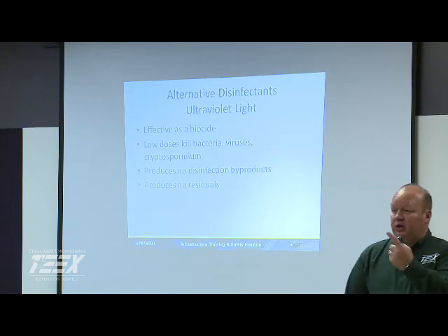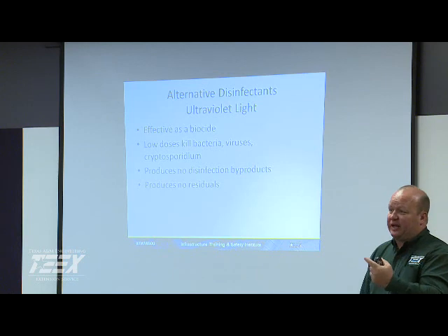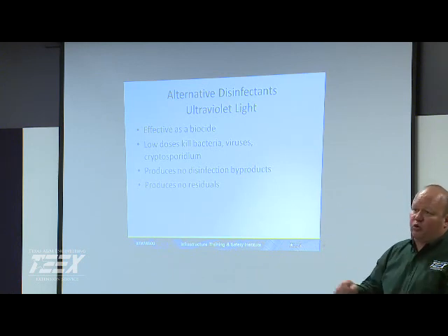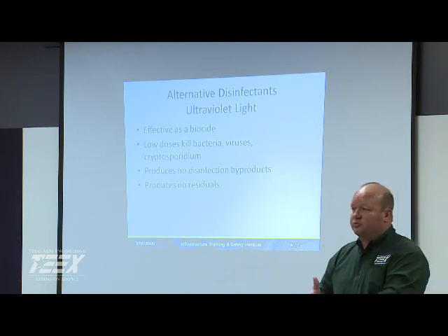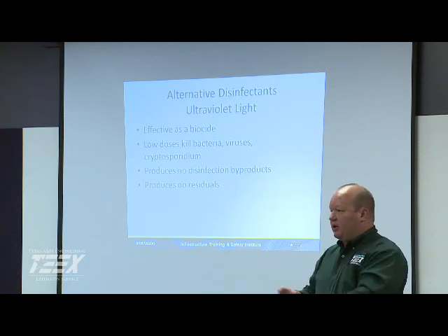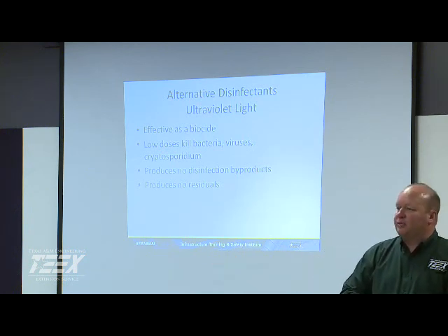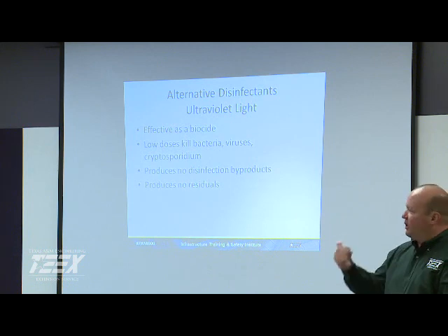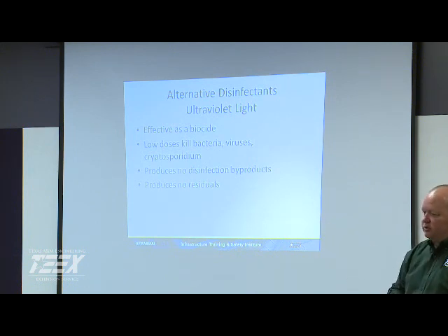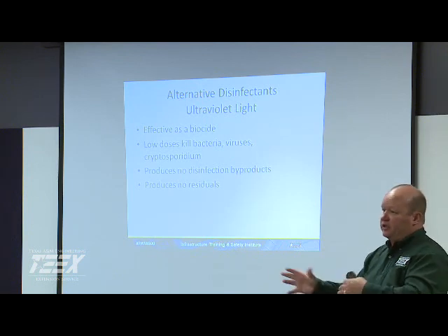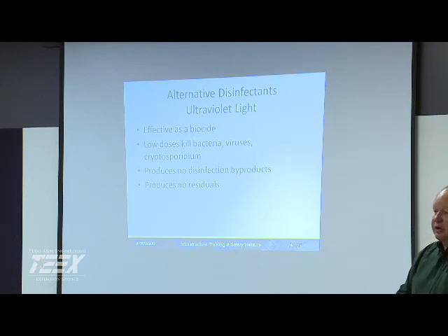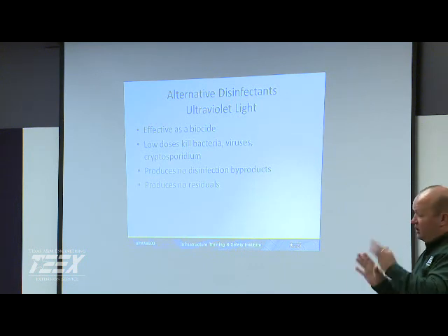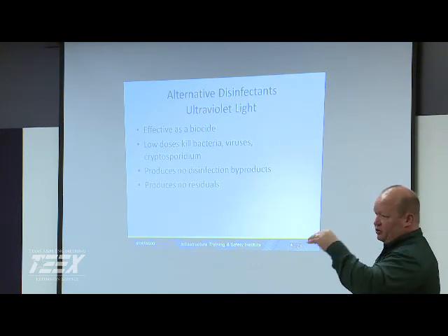Energy cost is a big one, and maintenance on it, you gotta use some pretty nasty acids to clean your quartz and stuff like that. The bulbs are expensive, you gotta keep up with your bulb runtime hours and all. We had some at one of our small plants, and it was a lot of work to keep it up to speed. Turbidity is a big issue, you have any kind of turbidity in there, and it really affects your penetrating power.